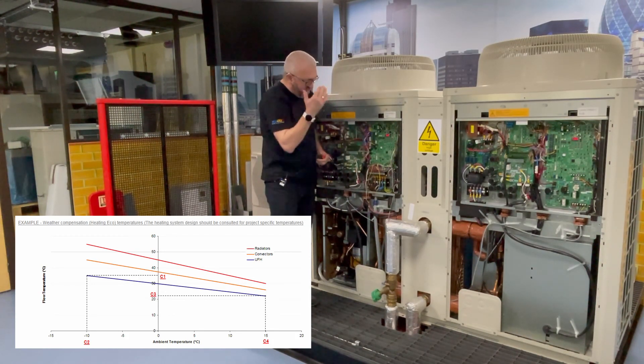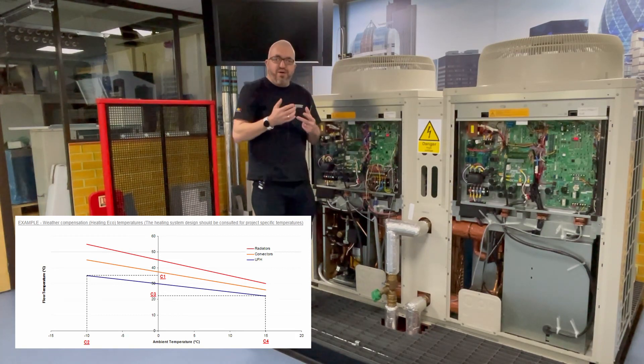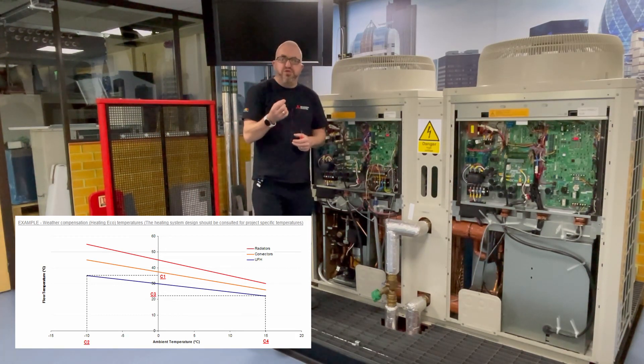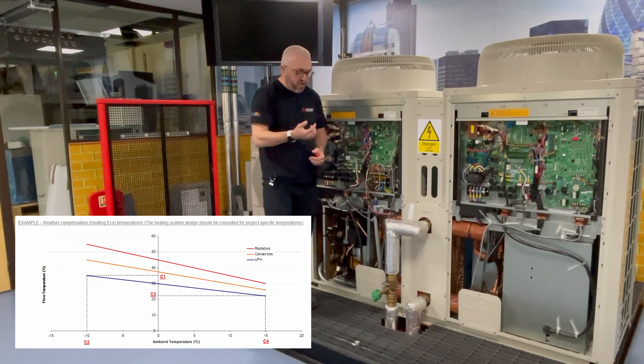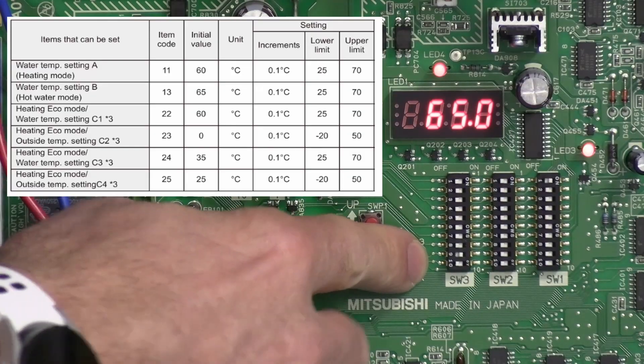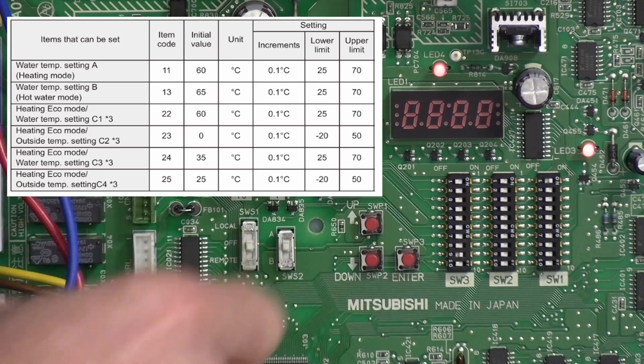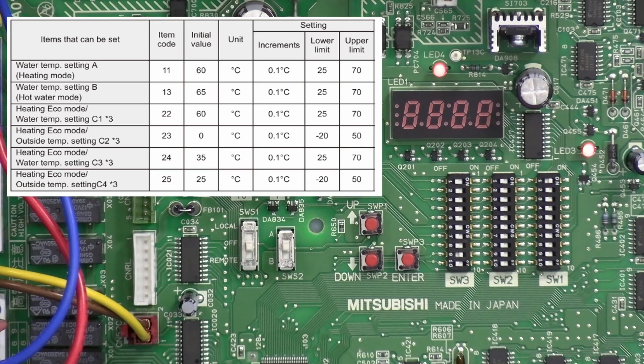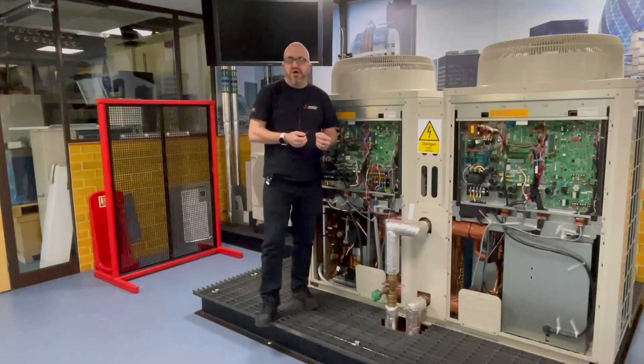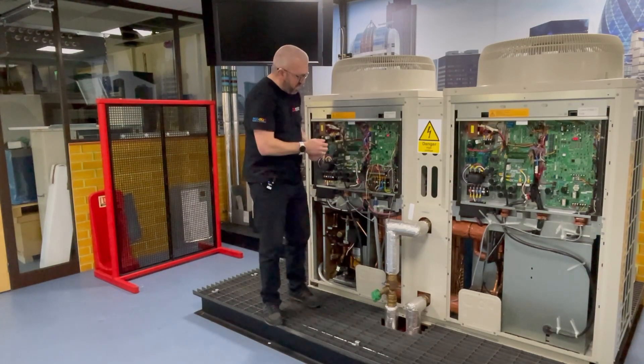We're going to say 65 degrees is our high flow temperature. Now we need to tell the system what ambient temperature we want it to achieve 65 degrees flow. So that's the next parameter, it's item 23. We're saying here zero degrees, so at zero degrees it's going to target 65 degree flow. Zero, I'd say that was a good setting, so let's leave that at zero.